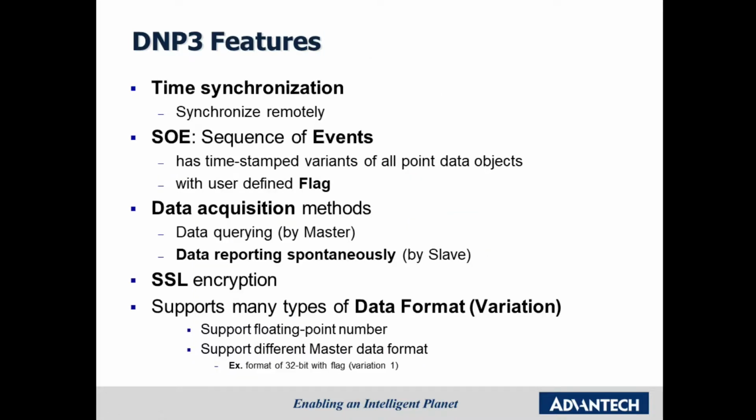And DNP3 has several features. The first is time synchronization. Users can synchronize their devices remotely. The second is sequence of events, SOE. It has timestamp variants of all point data objects with user-defined flags.